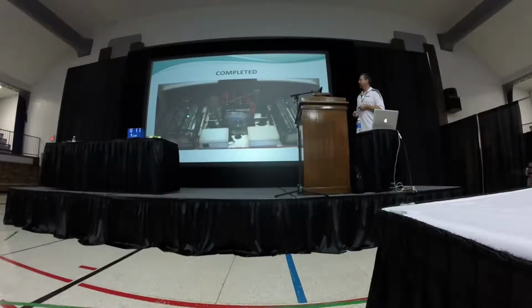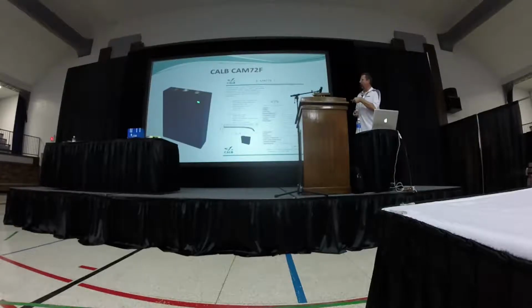The batteries are coated in a thin mylar heat shrink material, and the casing of the battery is actually aluminum. If you put a voltmeter between the terminals and the case, you do get voltage. We found that if you pierce that mylar coating, you'll get current flow to the battery pack. It's minor, very small, but enough to trip the GFI in the motor controller.